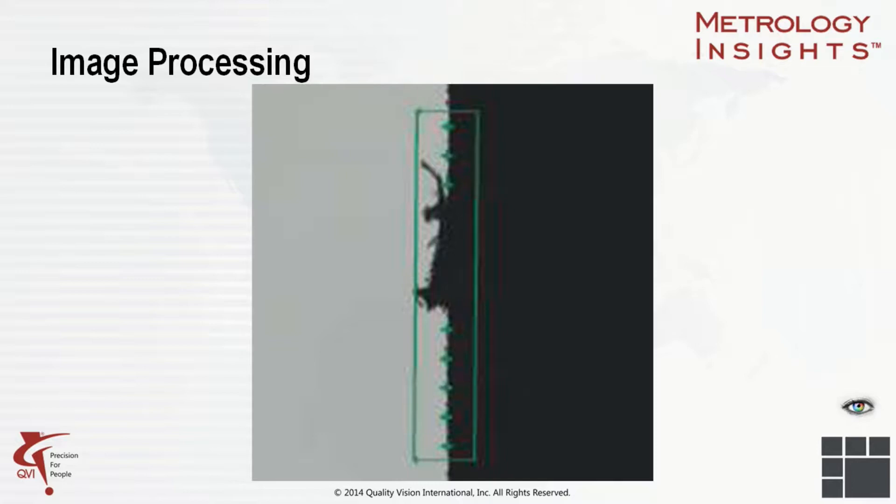Here we see an example of basic edge detection. In this scene, there is a lot of image data, most of it either all light or dark. What we're interested in is the area of transition between light and dark — the edge of the part. To speed up measurement, we can tell the measuring system where to look for an edge. The green box shows the search area used to tell the measuring system where to look for the part edge. In this case, we see the found edge, indicated by the green plus signs. We also see there is a defect of some sort, most likely dust or a burr, which can probably be easily removed and is therefore not important to the measurement.